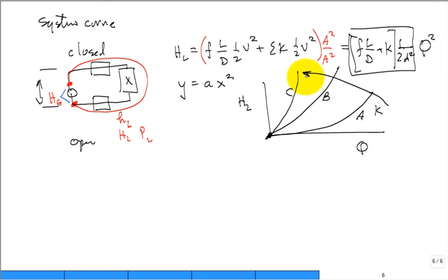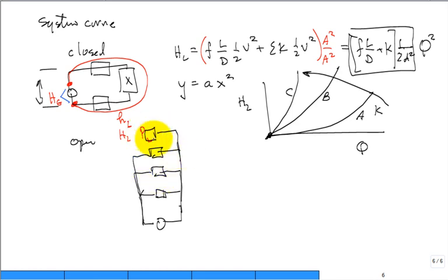One of the things that people will do is say, oh, I have a high-rise building, and I have a pump down here, and there's my supply, and I need to bleed off some and put it through this and then take it out and bring it back down, but then I got to go up higher, and I got to put it through here. Then I put it down here. Oh, I got to go over here. I got up here. You know what? This building is so tall that I need to size this pump so that the head gain across that pump can match the elevation gain that the system needs to provide. And so they'll say, well, I figure out that each one of these is balanced, so it's only 50 psi. But I need to move it from here to here, and maybe that's, I don't know, 30 psi. Well, I need a pump to supply both to push it through the resistance plus to push it up in elevation. Is that good logic or bad logic?